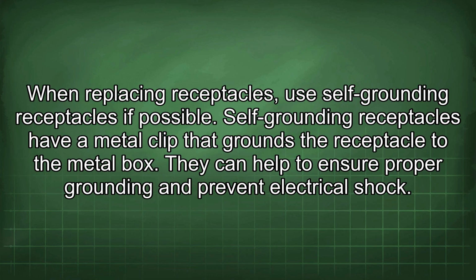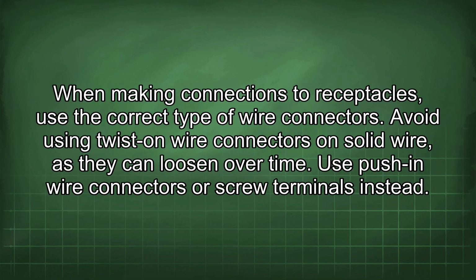When replacing receptacles, use self-grounding receptacles if possible. Self-grounding receptacles have a metal clip that grounds the receptacle to the metal box. They can help to ensure proper grounding and prevent electrical shock. When making connections to receptacles, use the correct type of wire connectors.